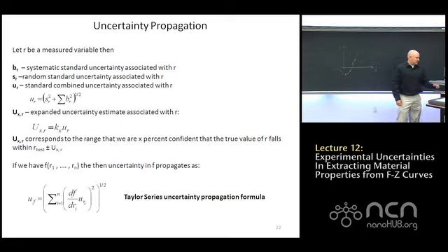If our sample is large enough, u is essentially a standard deviation. We can treat it like that, associated with a probability distribution function. Based on our number of samples, we can go from our standard uncertainty u, which doesn't have an associated confidence interval, to expanded uncertainty, which is capital U, which describes the uncertainty within a given confidence.